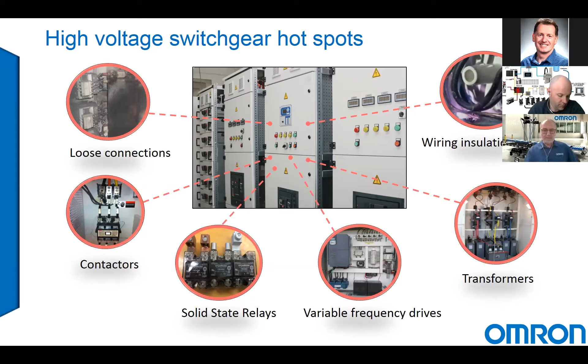So what we're offering is a system with actual IR cameras inside your control panel. They're very tiny cameras. I'll show you on my demo here. You can mount up to 31 per relay. They're all daisy chained on RS-485. They can be mounted with a magnet in the back, or on the control panel door. Once the door is closed, it will look inside in real time and show you a matrix of your temperatures, and give you an image of where the hotspots in your panel are, like you can see on the free PC software that we also offer. And obviously they have a dry contact alarm for a beacon on your control panel if you need one.